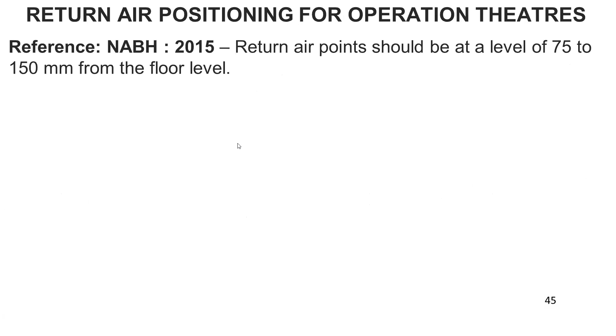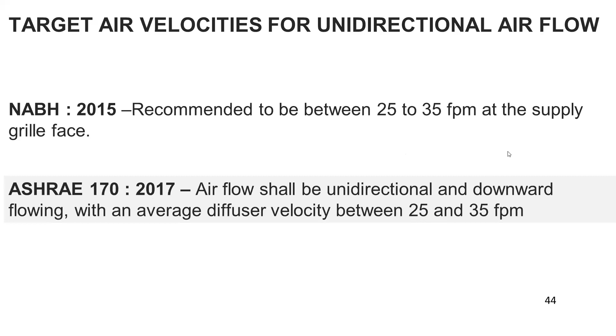okay, return air positions. Sorry. Target air velocities for unidirectional airflow recommended as per NABH is 25 to 35 FPM. Then ASHRAE 2017 says it should be 25 to 35 FPM. So this is what we are talking of on the laminar flow front.